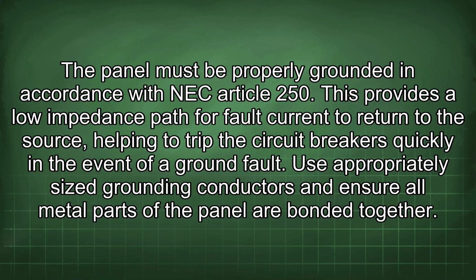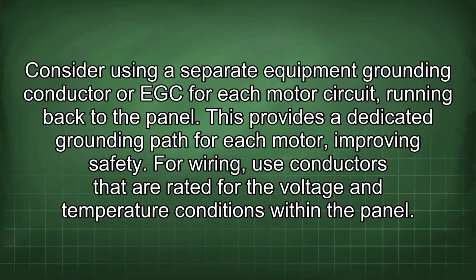Use appropriately sized grounding conductors and ensure all metal parts of the panel are bonded together. Consider using a separate equipment grounding conductor, or EGC, for each motor circuit running back to the panel. This provides a dedicated grounding path for each motor, improving safety. For wiring, use conductors that are rated for the voltage and temperature conditions within the panel.